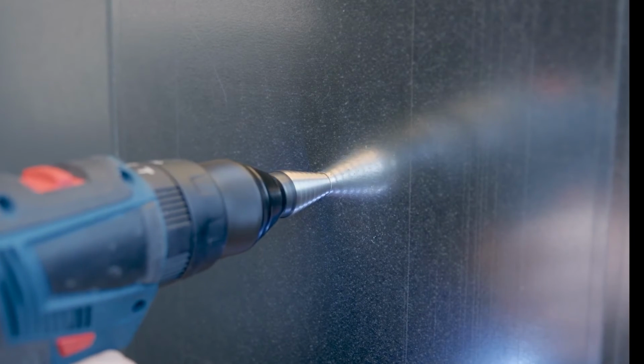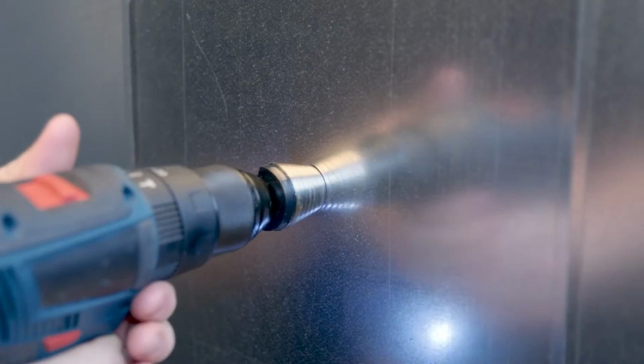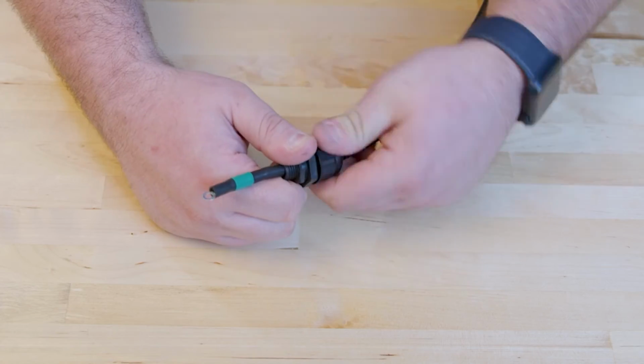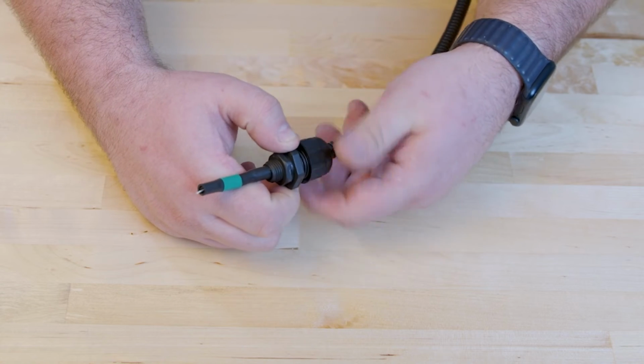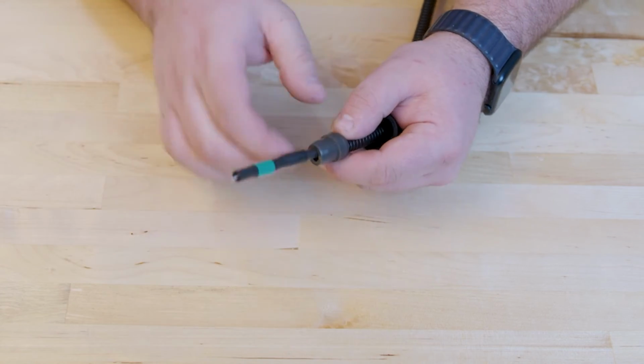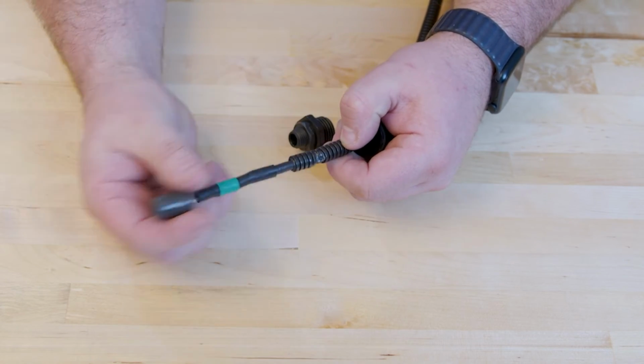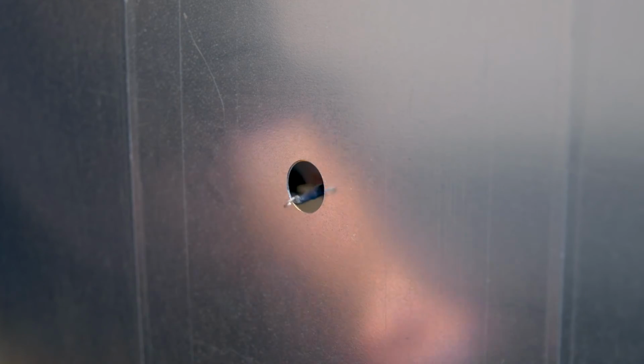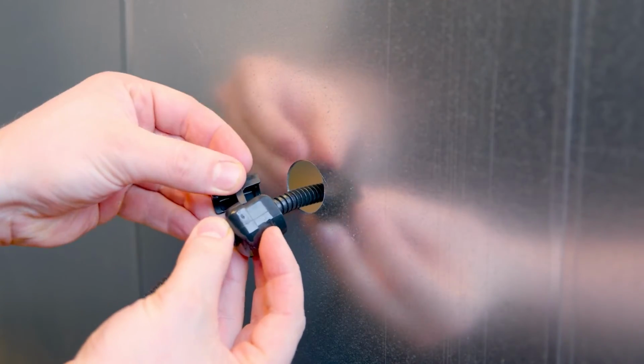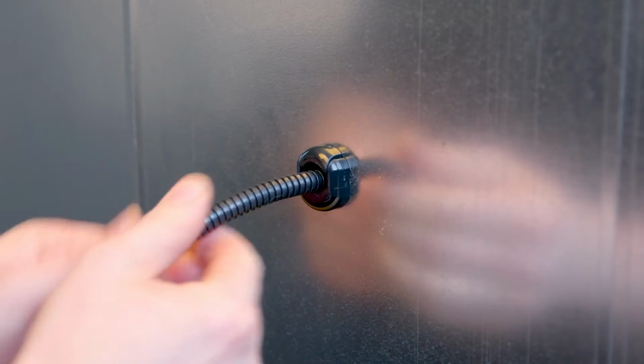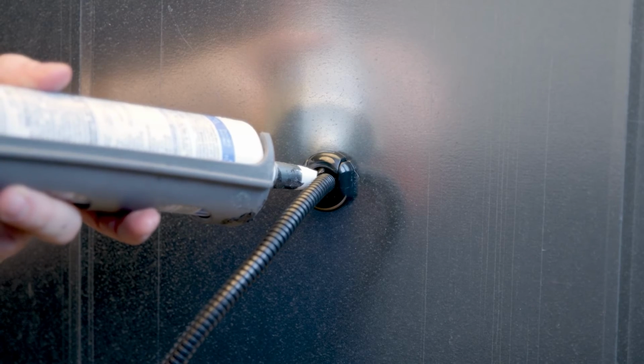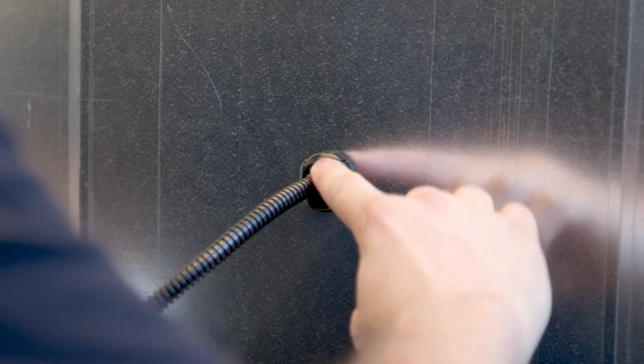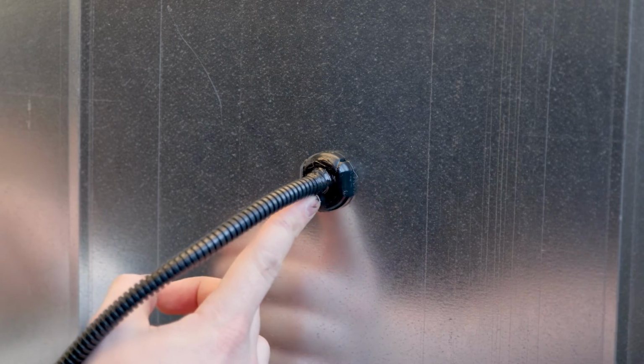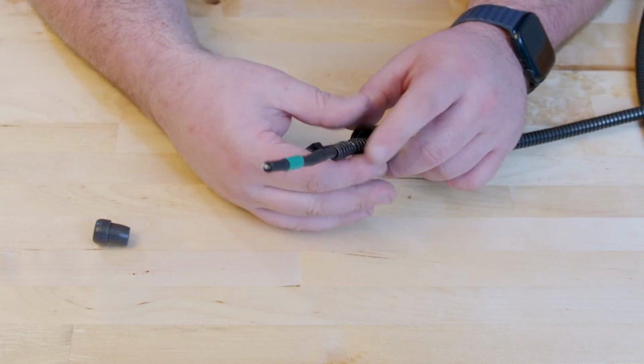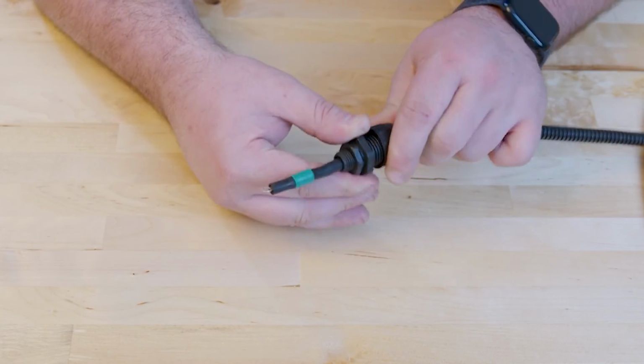First, drill a hole appropriate to the size of cable gland you are using. If applicable, remove the pre-installed cable gland from the end of the cable with the smaller ring terminal connector. Feed the cable through the hole and attach the grommet and secure it to the surface. Use sealant to prevent air leakage and to secure the cable in place. If removed, ensure that you reinstall the cable gland that came with the high voltage cable.